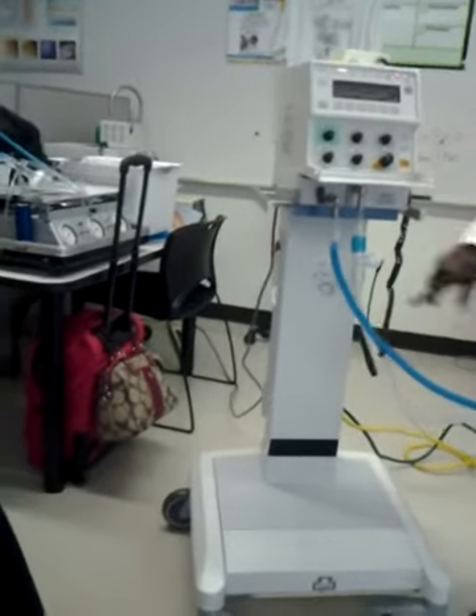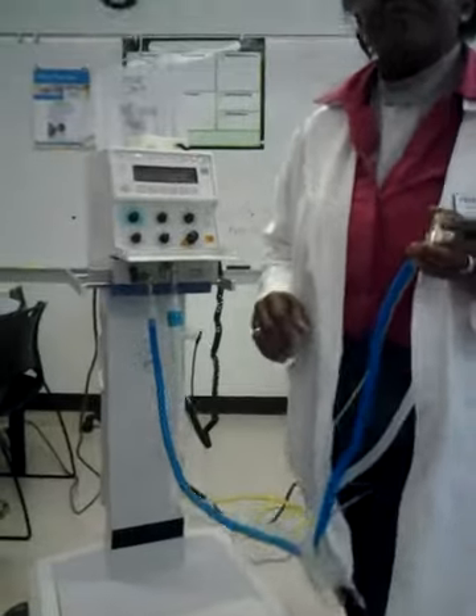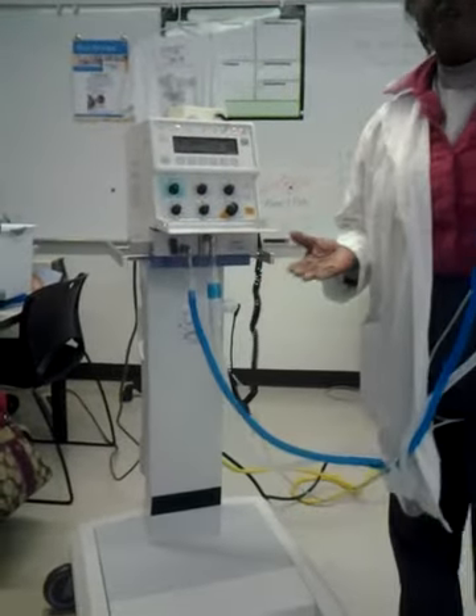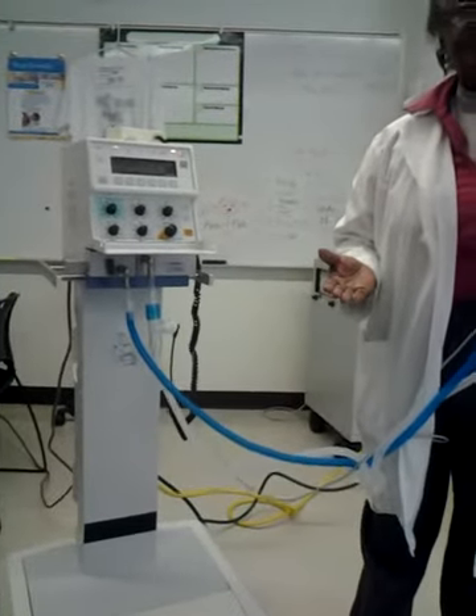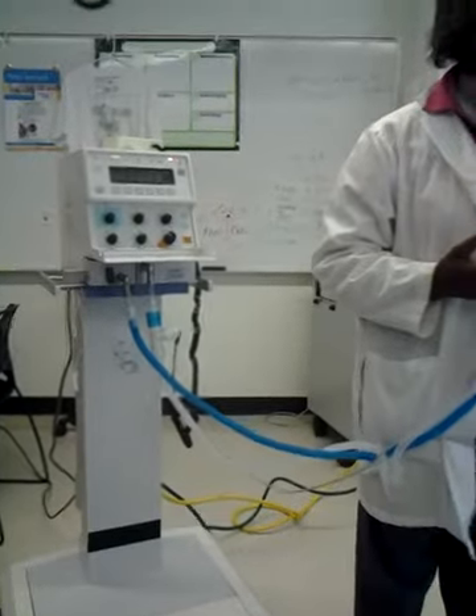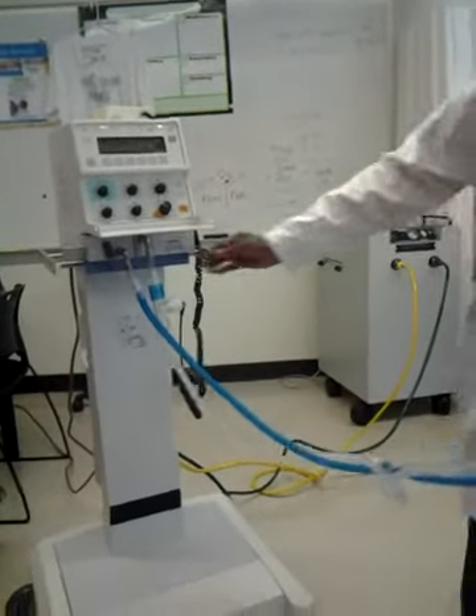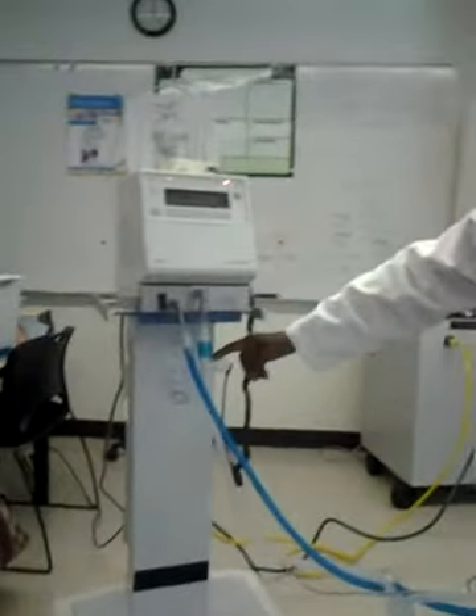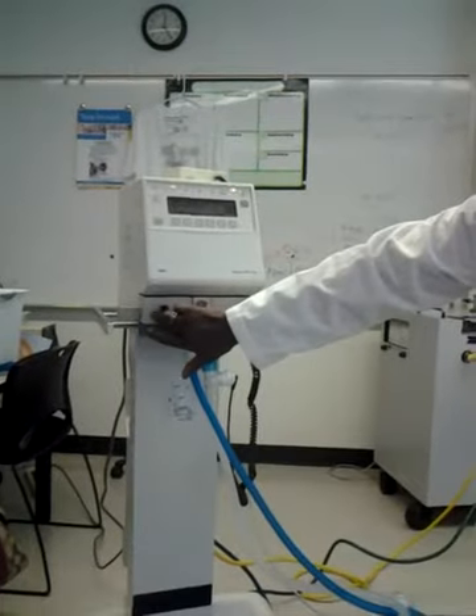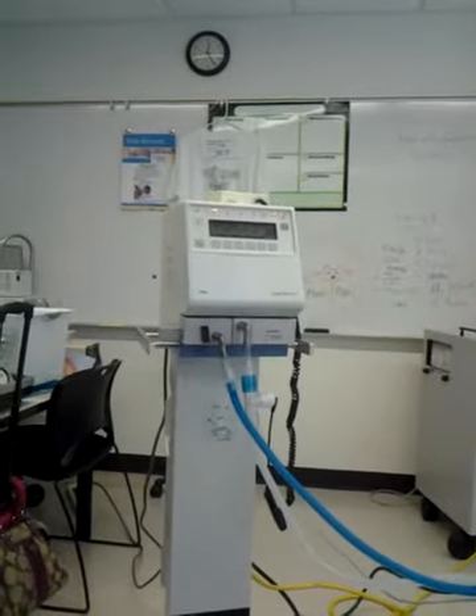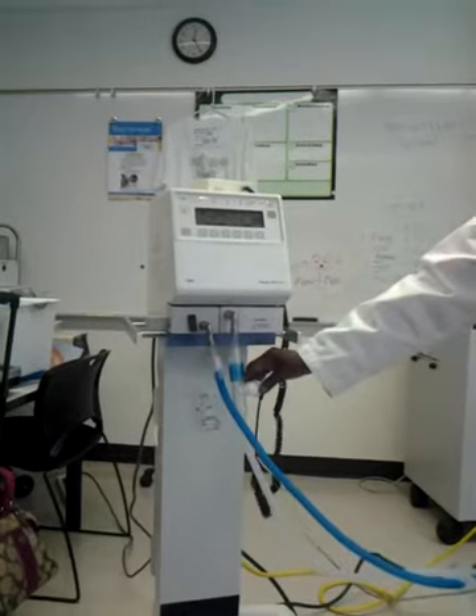So now it's just going to the patient. It would be humidified. Yeah, you would also have to know that you would put a humidifier on. Are you getting that? The oxygen analyzer's right there. Inspiration comes out of the machine to the patient. This is your inspiratory limb. And would you have another analyzer here? No, just right here, before it goes to the patient.